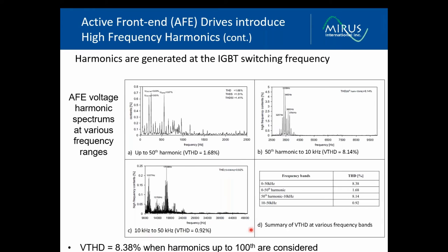If we go on in the 10 kilohertz band, again, there are IEC standards in this band that require filtration being done, and so the levels are lower. But in the range from 50th harmonic to 10 kilohertz, there are no requirements, no IEC or IEEE standards or marine standards that are going to limit that, except for ABS that requires this to be considered when active devices are used. So total, more than 8.3%, but the manufacturer is going to highlight and point to this 1.68% because that's 0 to 50th.